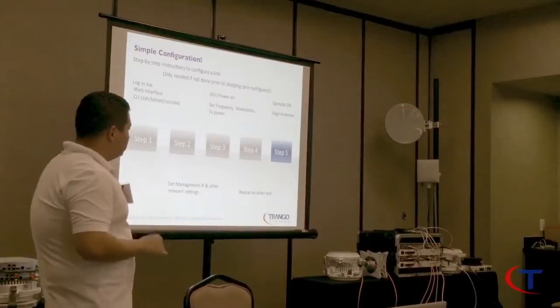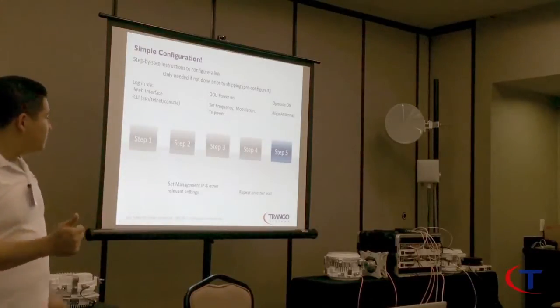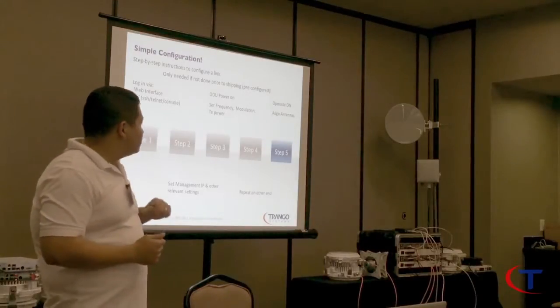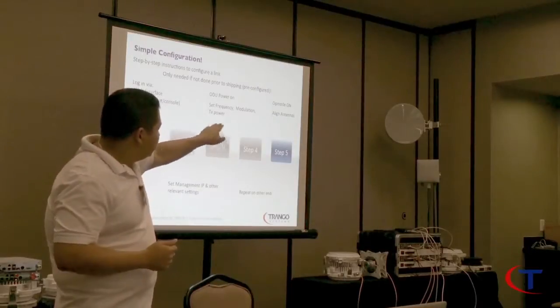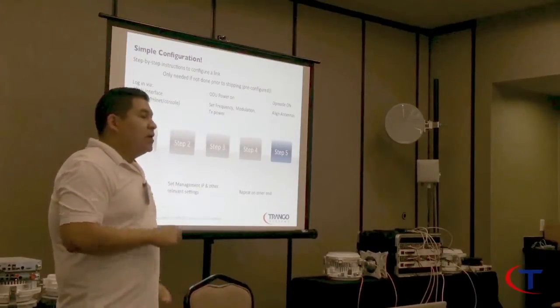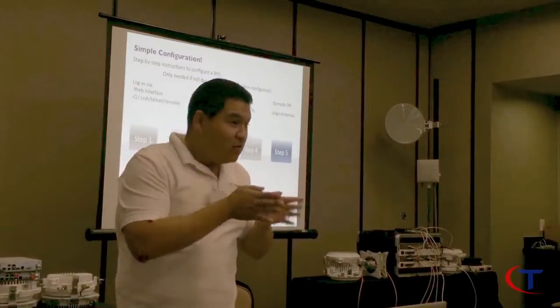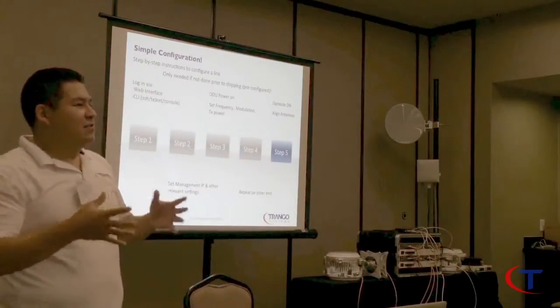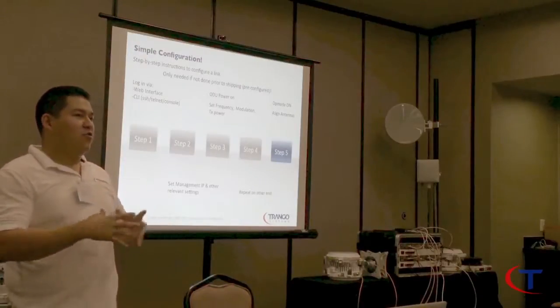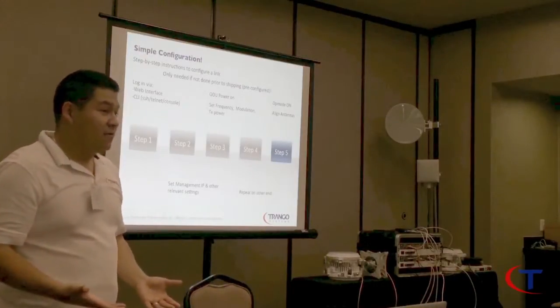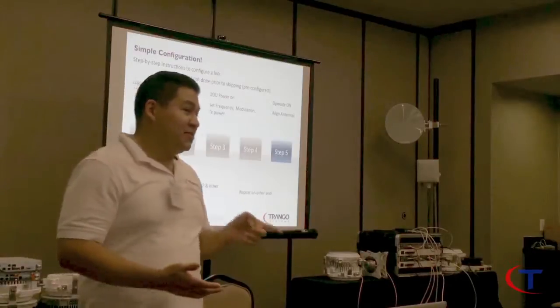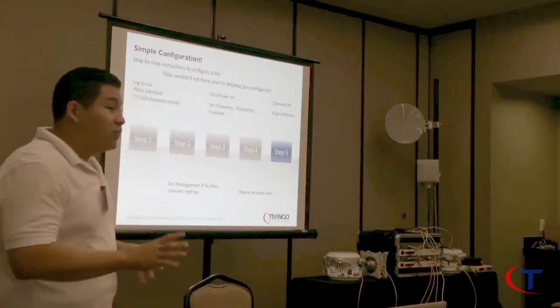After you set those, set your frequencies. ODU power on. Set frequency, modulation and transmit power. If you do not turn the ODU power on, the actual IDU or OMU is going to tell you, I cannot set the frequency. Why? Because I don't know what frequency range I can set. Okay? So you remember, you must turn it on. You don't have to transmit.